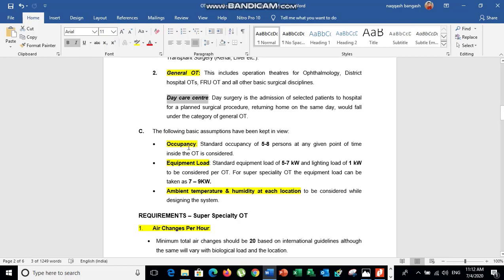For load calculation and air requirements, the occupancy is five to eight persons. The heat load per person is 250 to 300 BTU per hour. Equipment load is five to seven kilowatts, and lighting load is one kilowatt. For super specialty OTs with special equipment, the equipment load increases to seven to nine kilowatts. These values are used in cooling load calculations.